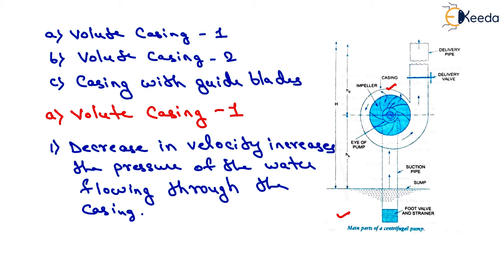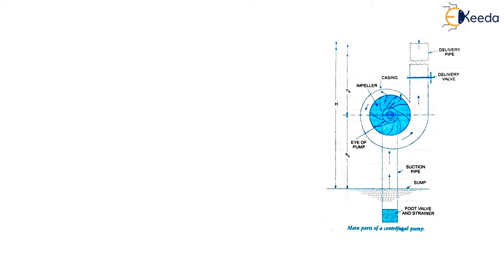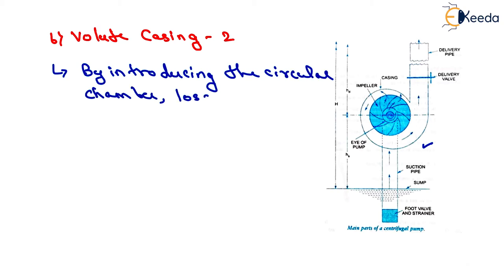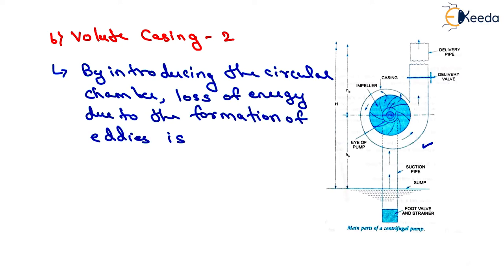Now we will see volute casing type 2. If a circular chamber is introduced between the casing and the impeller, the casing is known as volute casing type 2. By introducing the circular chamber, the loss of energy due to formation of eddies is reduced considerably. Thus the efficiency of the pump is more than when only volute casing type 1 is provided.